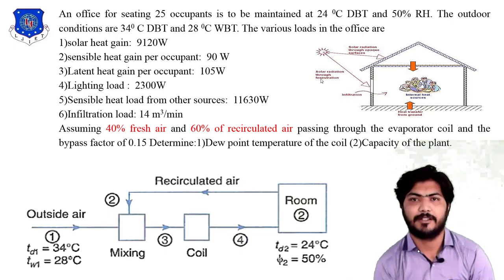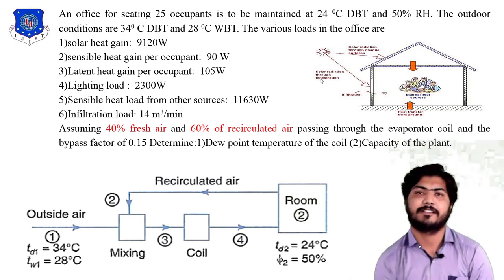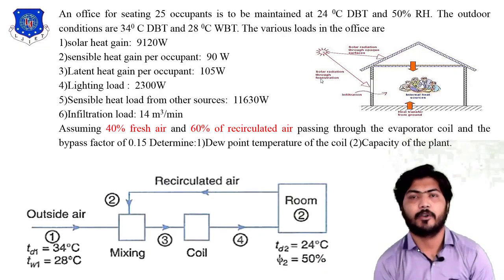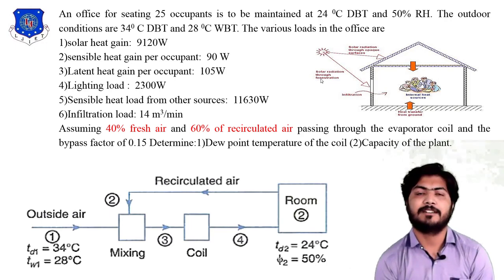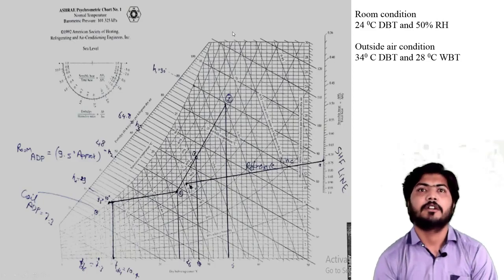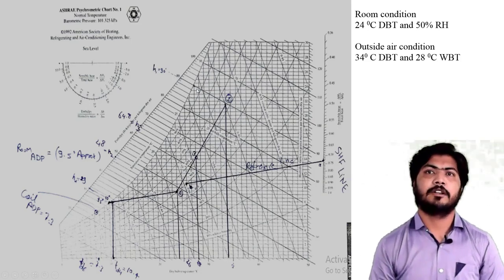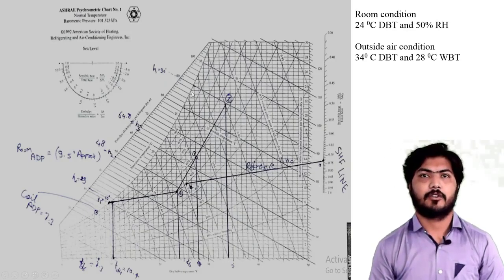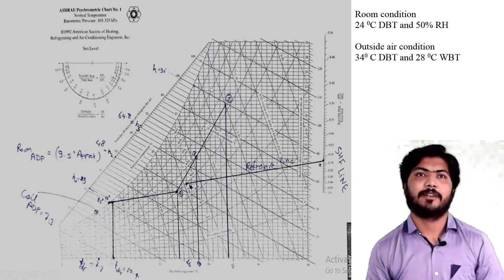For point 2, the dry bulb temperature is 24 degree centigrade — a vertical line — and relative humidity is 50%, which is a curve line. These two lines intersect at point 2 on the psychrometric chart. I am drawing the psychrometric chart: for point 1, the inclined wet bulb line at 28 degree centigrade and the vertical dry bulb line intersect at point 1. The enthalpy at point 1 is 90 kJ/kg. Point 2 is also located and confirmed.